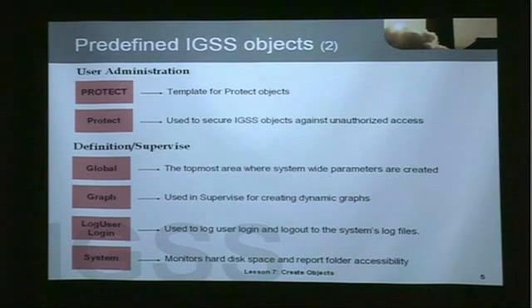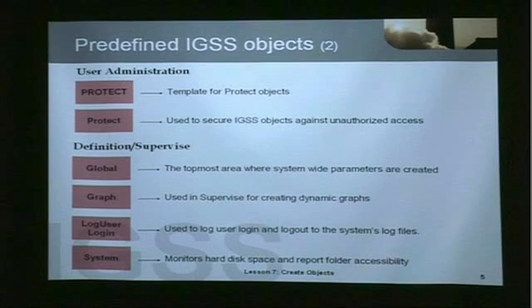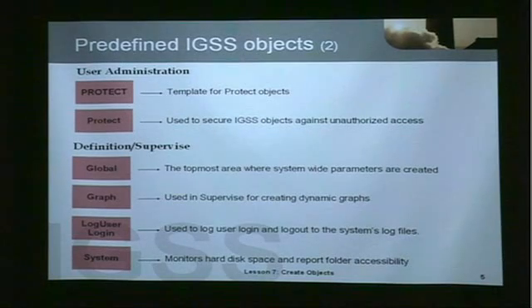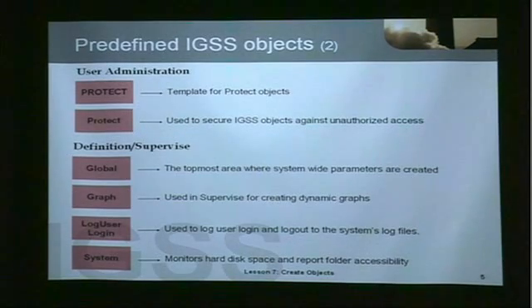In the definition supervise modules, we have the global object, which we've seen in the presentation of areas and diagrams — this is the topmost area where system-wide parameters are created. Then we have an object called graph, used in supervise for creating dynamic graphs that the operator typically uses while monitoring the plant. Then we have the log user login object, used to register and identify users that log on and off the system — the prerequisite being that the configuration is set up with the user administration security module. And finally, the system object, which monitors hard disk space and report folder accessibility.